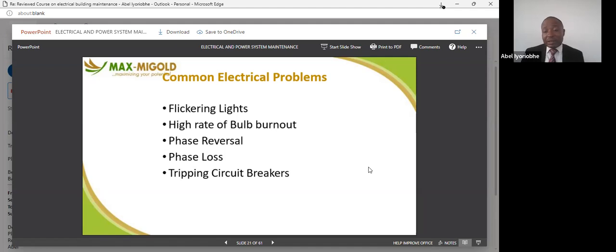Another problem is phase reversal. Maybe public supply officials came to address a fault, and on terminating back, they mix up the phases, so your elevator, instead of going clockwise, is going anti-clockwise. That means the lines are not well positioned. So what you need to do is call them and relay the issue, and they will come and fix it. Another one is phase loss.